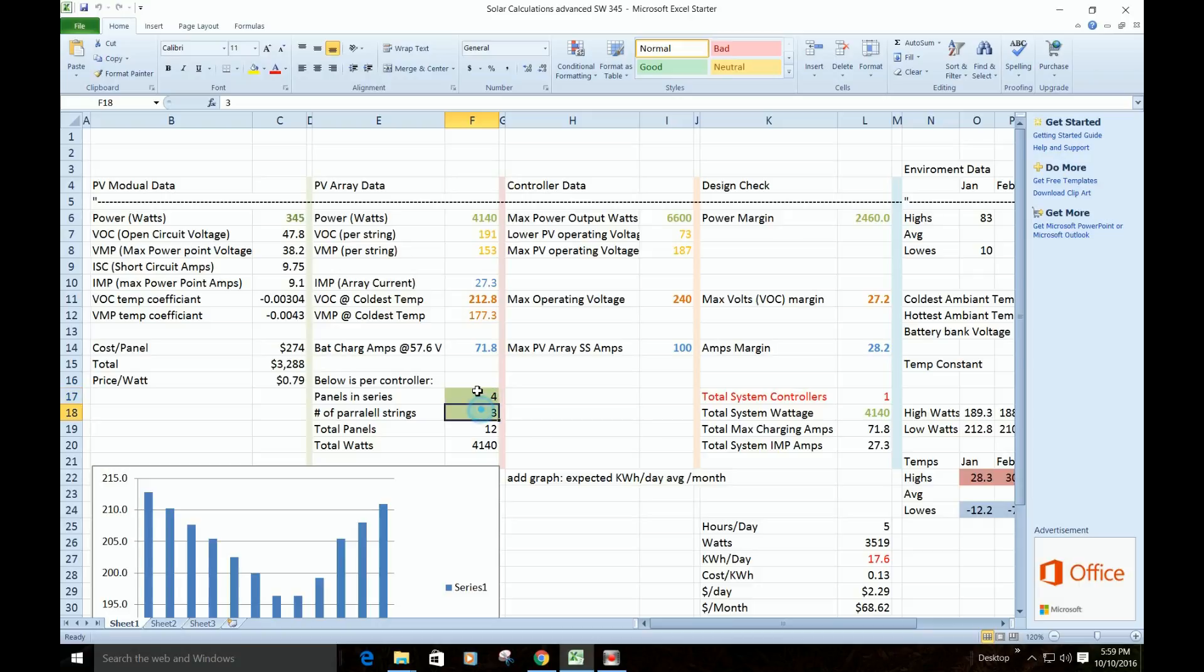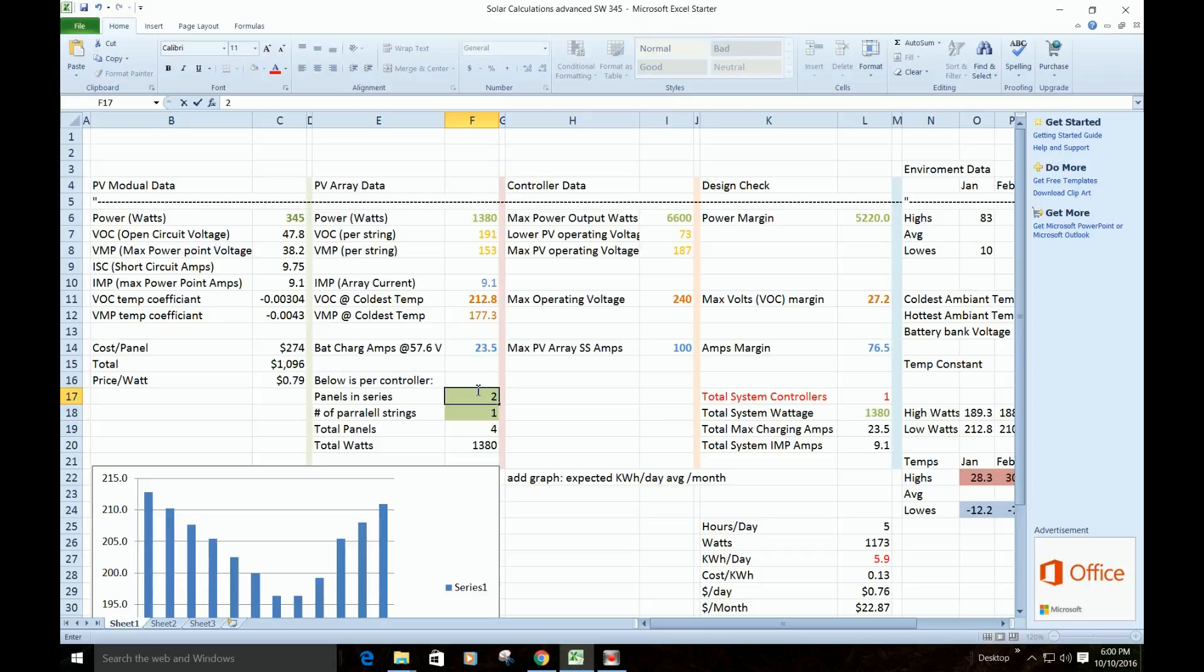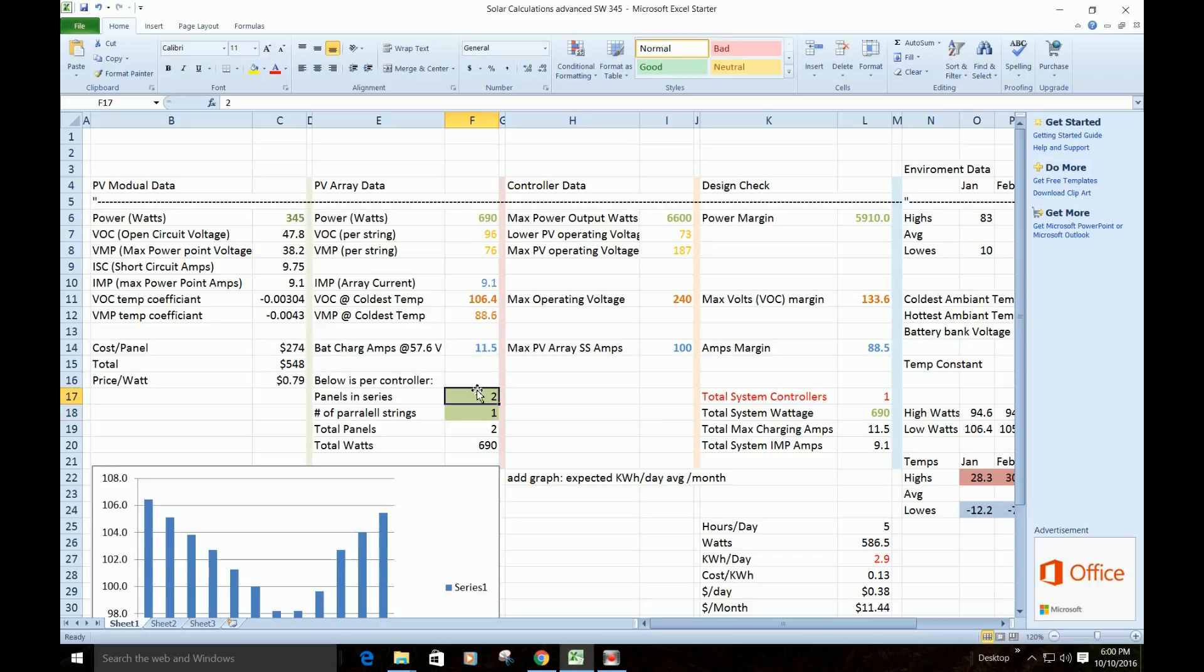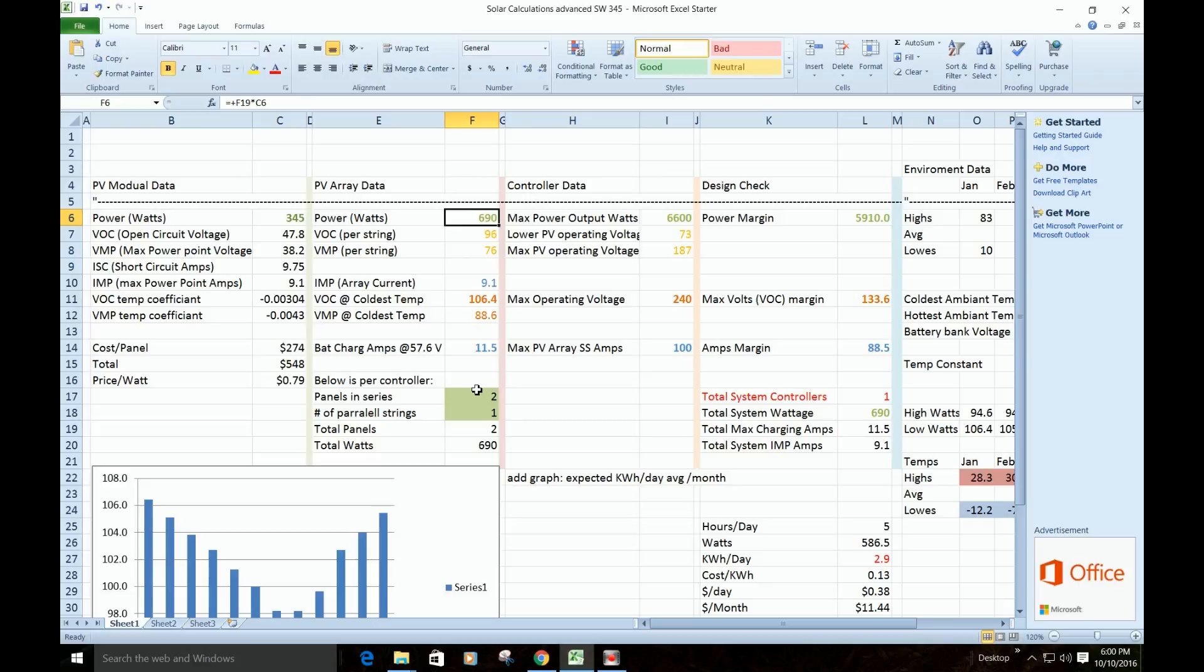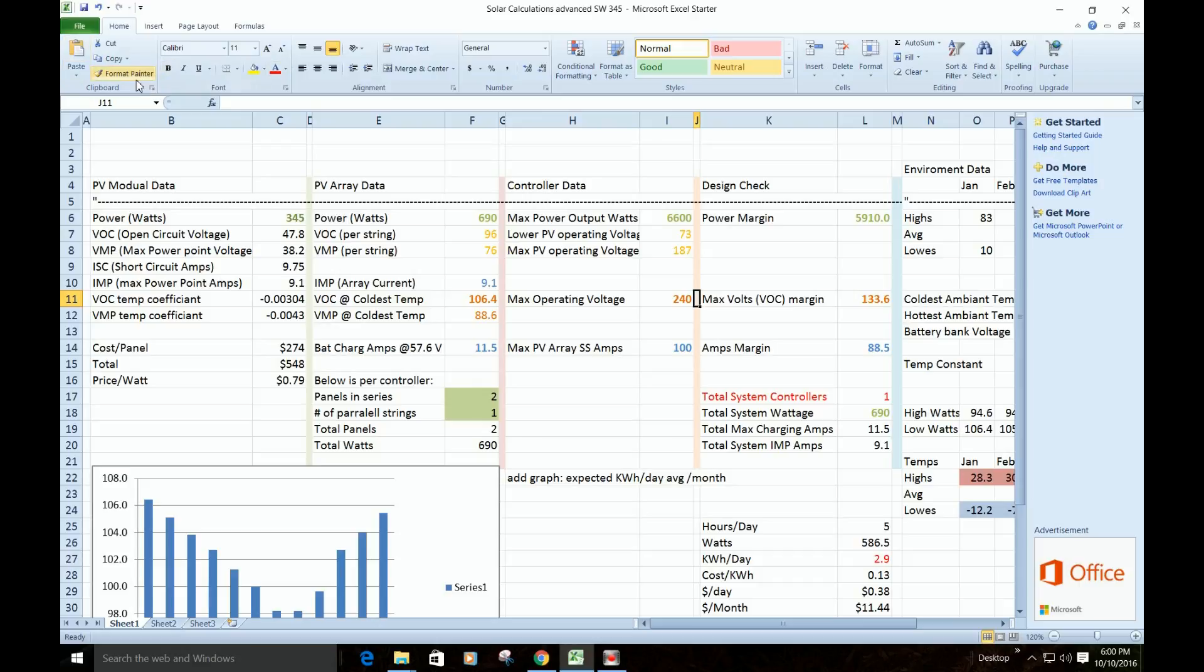So this is where we can plug in some numbers and play around here, and the system will calculate the rest. So let's start with two panels in series, just one string. And then we can go up here and say, well, then we'd have 690 watts, and we'd have 106 volts for the open circuit coldest temperature, which is well under the 240. So here's your cushion. You got 133 to spare. 11 amps out of 100, you got 88 amps to spare, so we're nowhere near.